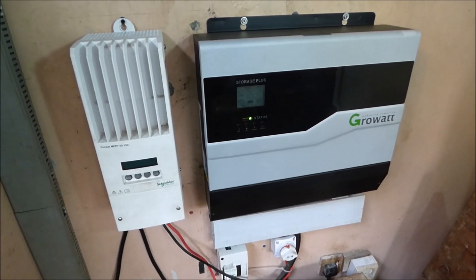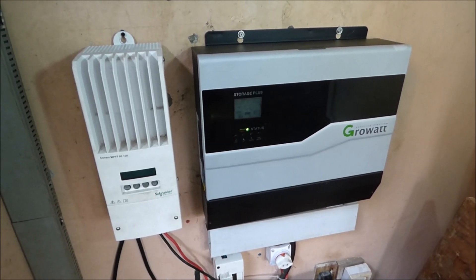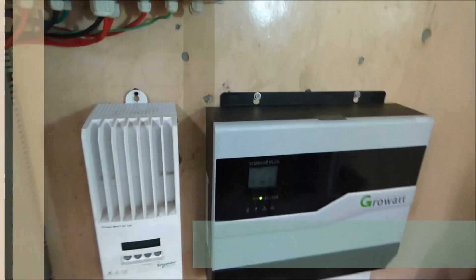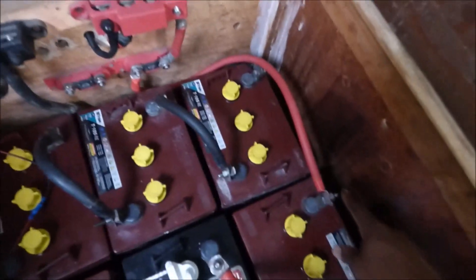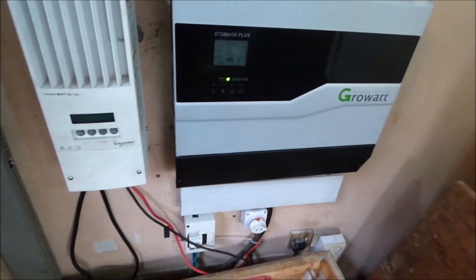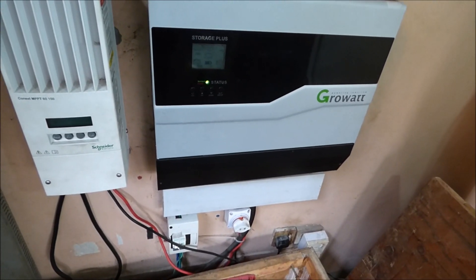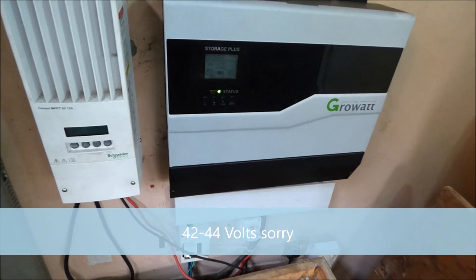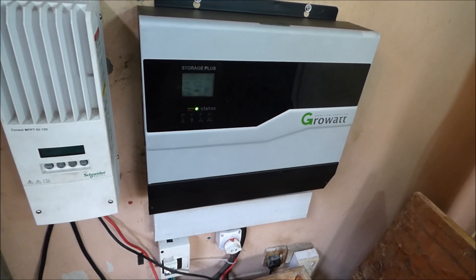One of the things we like to do is set a hard shutdown or cutoff voltage for our batteries — we usually set it at 48 volts. This is a 48-volt inverter; all our batteries are wired in series with the positive here and the negative there. We set our cutoff at 48 volts, but this inverter does not cut off until about 42 volts, which is very bad for our batteries.